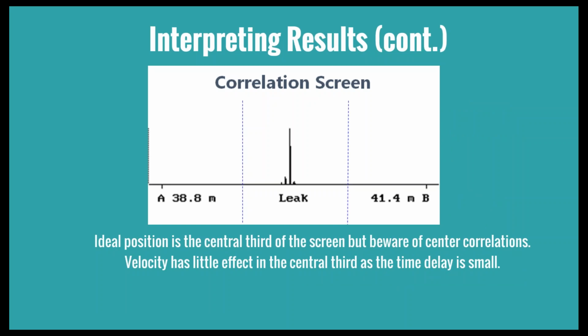So again, just a screenshot of what the ideal position is. When your correlators are picking up a noise, and you want to try to get it as center as possible. But with this type of situation, the velocity of that noise has little effect as the time delay is small when you're doing a correlation in that respect.